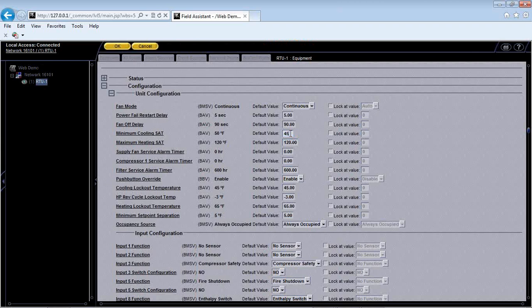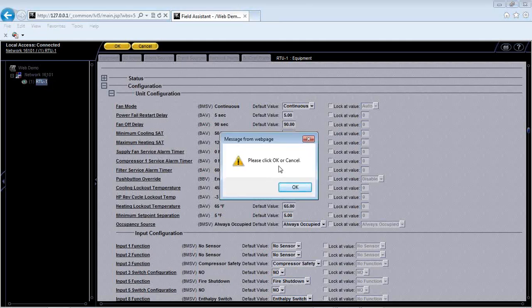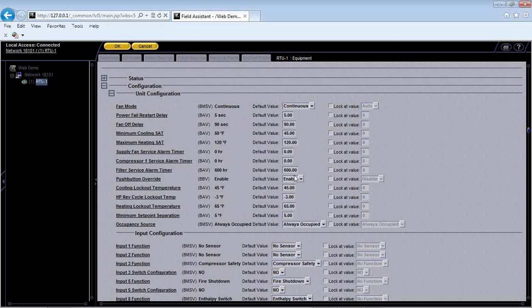Okay, so I can just click on that number and I can type in, say, 45 degrees, and that will switch that value. One thing to note overall is any change that you make, you notice I just typed in 45, you'll see these boxes come up, these OK and cancel. I have to click either OK or cancel before I can try to move to a different screen, okay? So if I wanted to go back to my network screen on the left here, if I click it, it's going to say, nope, you need to hit OK or cancel in order to make your change, all right? So I want to change this to 45 degrees for my minimum cooling supply air. I need to hit OK. Once I hit it, it'll disappear, and I'm good to go. I can switch screens. If I want to change my maximum heating to, let's say, 95, I'm going to type in 95. Let's say I don't want to change it. I just typed it in wrong. I can hit cancel, and it's not going to take that 95 degrees, okay? So it's just something that you have to remember. If you ever get stuck and it says, please click OK or cancel, you got to hit OK or cancel.